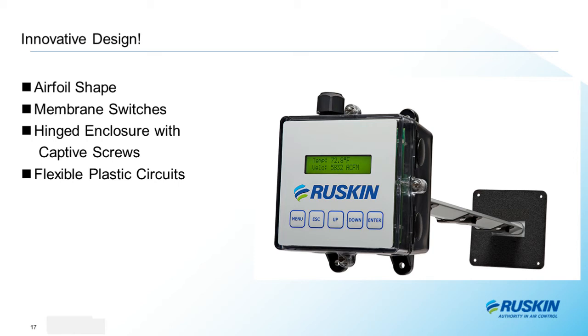Pin-protected, tool-free access to the menus with surface-mounted membrane switches. Hinged enclosure with captive screws so the cover doesn't get lost or misplaced and the screws don't get lost. We went to flexible plastic circuits with conformal-coated thermistors to provide the greatest tolerance for wet environments and the most durable sensors ever. All probes are hermetically sealed and water is not an issue. Hose them down if you want. It will not damage or degrade the sensors. Just make sure you've ordered the NEMA 4 option before turning the hose on the interface enclosure.